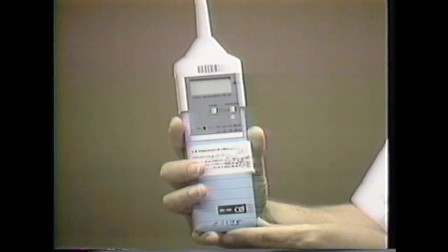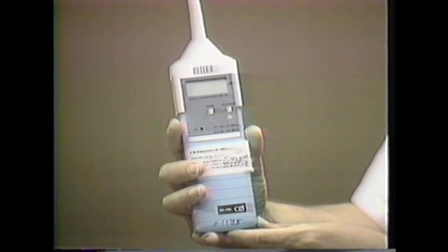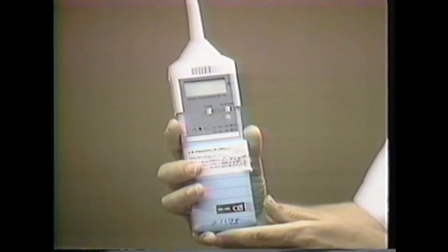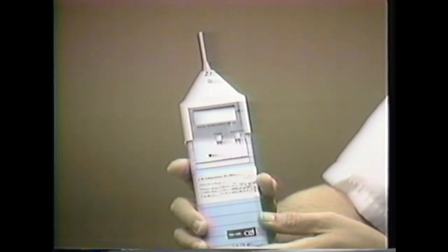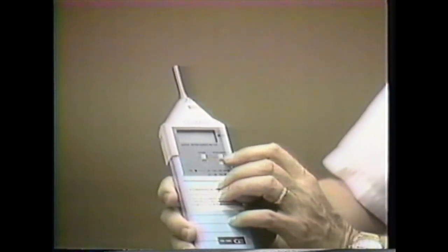The instrument that I have here is the basic standard sound level meter. It's a Type 2. Type 2 means plus or minus 2 dB error according to the ANSI, American National Standards Institute, guidance for these instruments. So we could be off by plus or minus 2 decibels from the real value. The microphone here is protected by a plastic cover, which I'm now going to remove. And that cover is very helpful in preventing the microphone from being bumped or damaged, and it's very sensitive to that type of trauma.